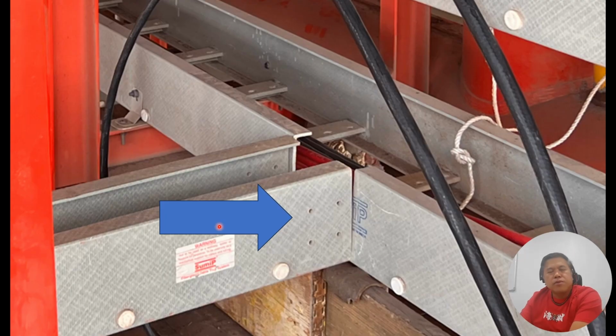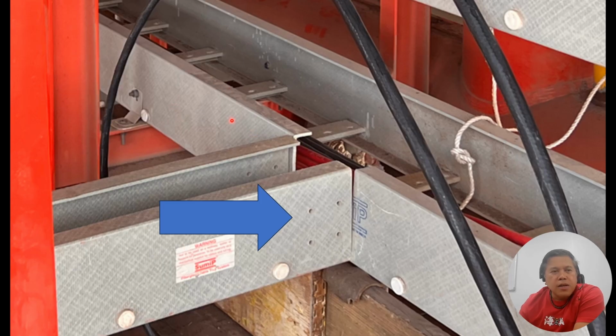So how about this? When you inspect this tray, basically all the QC will do the inspections of the installation of the cable tray, and you found this kind of installation that we are not accepting. So we need to provide fittings here.